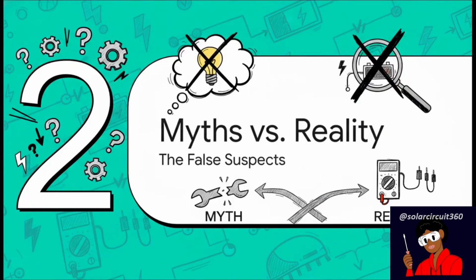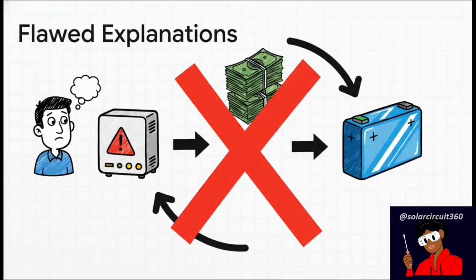Moving on to Section 2, Myths versus Reality, the false suspects. Before we lock up the real culprit, we need to clear the air on some overly simplified advice you see everywhere online. You know the type. People focusing purely on the error code, telling you your battery voltage is simply too low, so just replace the whole battery, or check the settings, or just assume the inverter is defective. While these guesses might hit the mark occasionally, they completely miss the root cause. Following this kind of flawed advice is going to result in hundreds of dollars down the drain, only for the exact same shutdown to happen again.